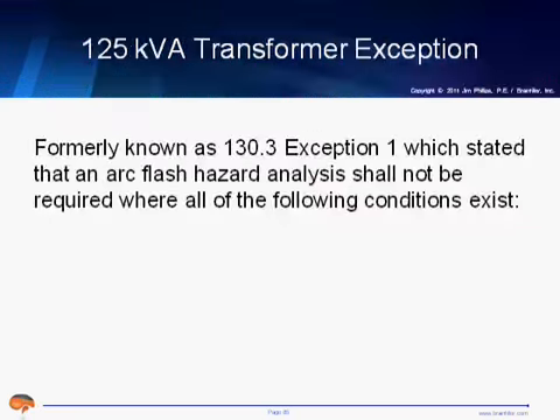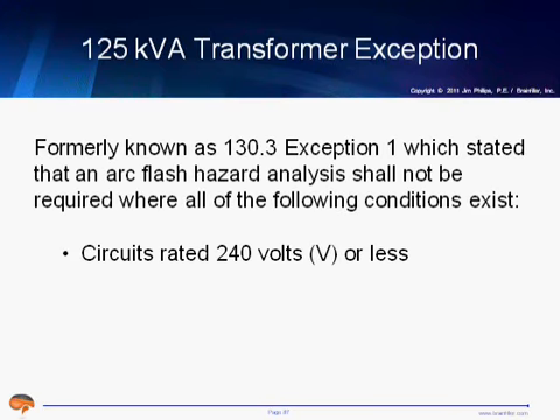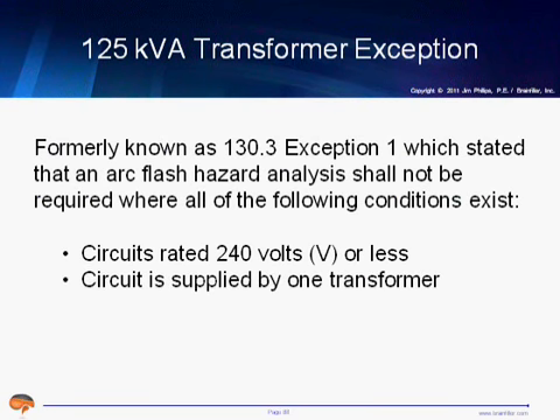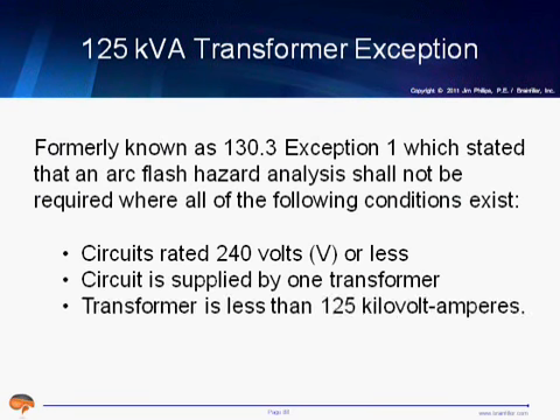The 125 kVA transformer exception, as many people call it, has caused a lot of discussion. Formerly, Section 130.3 had an exception that said circuits rated 240 volts or less supplied by one transformer, with that transformer rated less than 125 kVA, did not require an arc flash hazard analysis. This was actually language that was originally in the IEEE 1584 standard, and in IEEE 1584 it's less than 240 volts. When it made its way over to 70E, it became 240 volts or less.